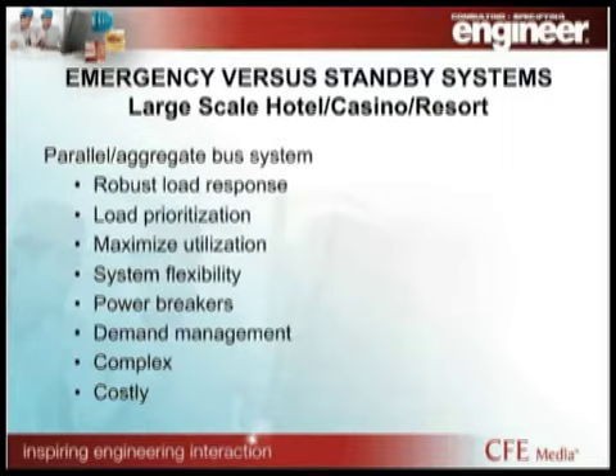And we're talking about a parallel or aggregate bus system. One of the major benefits of it is really robust load response. Gerald talked about the 10-second requirement, which is also in Article 700. One of the ways that we would typically set the system up is that your load bus would be serving power to the source under normal operating circumstances. So you would have a utility feed that ties to your load bus, then you would have a gen main, and that becomes your transfer pair between the generator source power and the utility source power. But for your large-scale loads that we would have in the 702, you can delay those until you have an engine count online that you're comfortable is going to be able to deal with the starting characteristics of that bulk load as you close those devices in. So load prioritization, you can do some really interesting things.